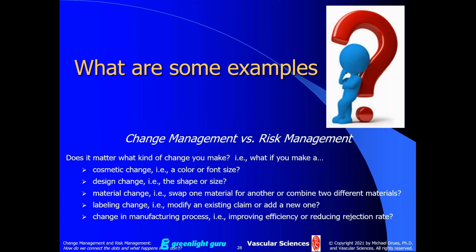And by the way, it doesn't make sense to me, this is sort of a criticism of the design controls, to separate the design of our device from the manufacturing process we use to make it. To me, those two things are intimately related to one another. So as our 510K devices are becoming more technologically complex, and as our manufacturing methods to make them are becoming more technologically complex, I think there are some potential advantages of asking FDA to be a part of that evaluation process for the 510K or the de novo submission, but it's not on the books yet. But it might be.